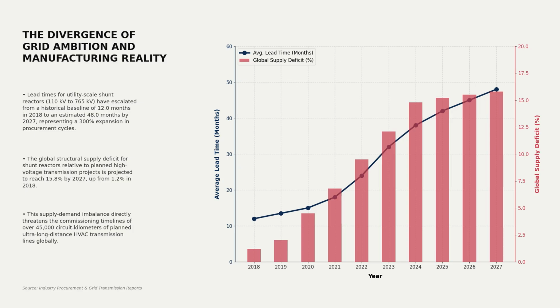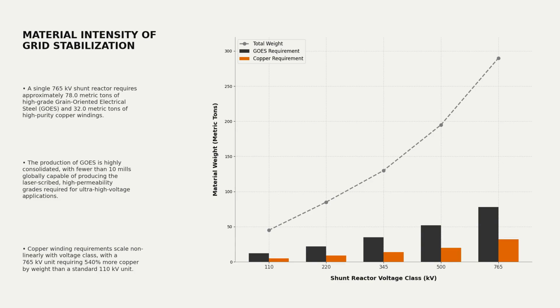The structural supply deficit is projected to reach 15.8% by 2027. This bottleneck directly threatens the commissioning of over 45,000 circuit kilometers of planned transmission lines. This bottleneck is driven by extreme material intensity. A single 765 kilovolt shunt reactor requires 78 metric tons of laser-scribed grain-oriented electrical steel and 32 metric tons of high-purity copper.